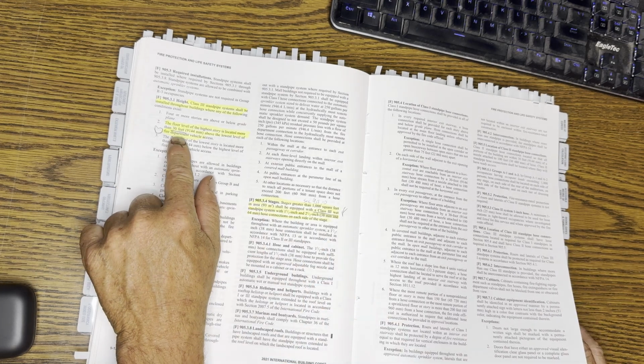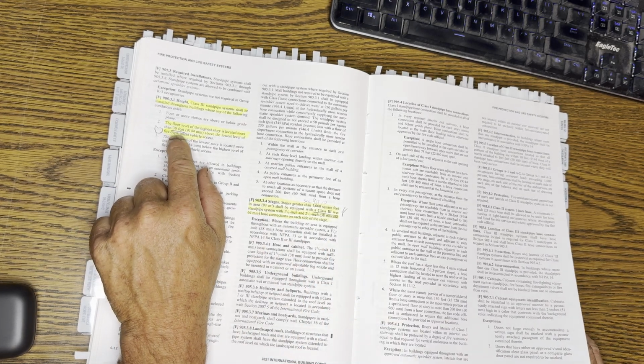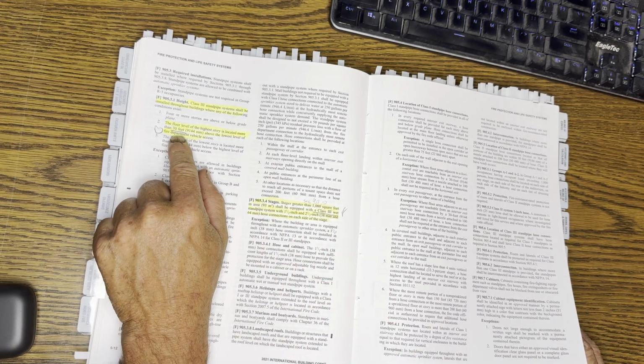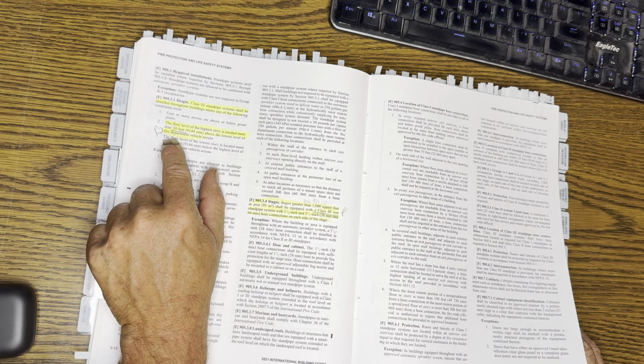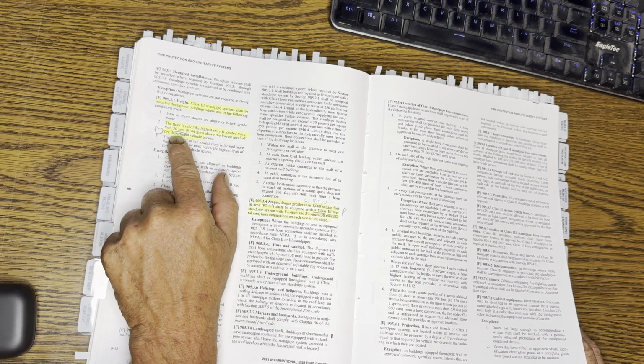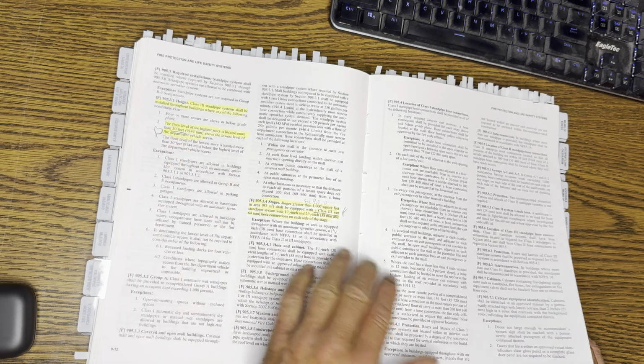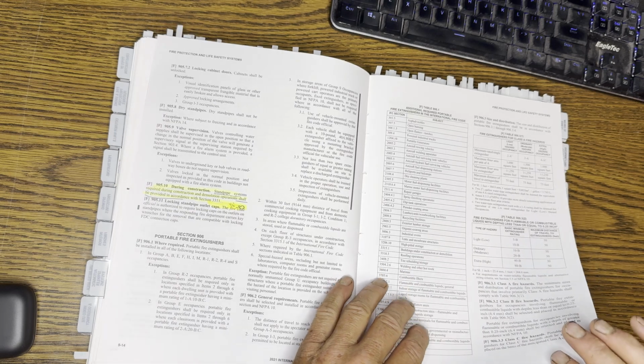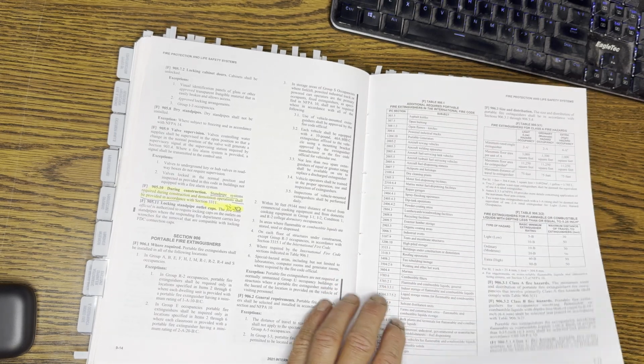The other thing, the magic number to keep in mind is 30 feet. If your floor level is above 30 feet over the level of exit discharge, the fire department vehicle access level, then you have to have a standpipe. And that is included for buildings under construction. Keep that in mind. So you got to do something. 30 feet is kind of a trigger magic number.